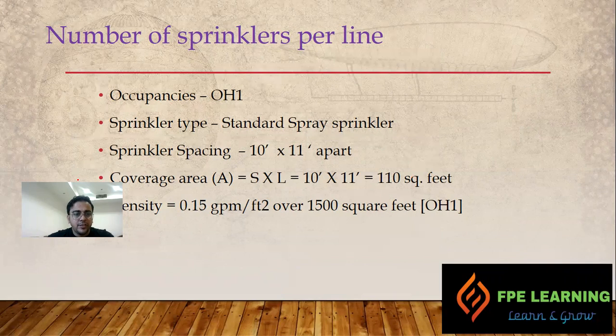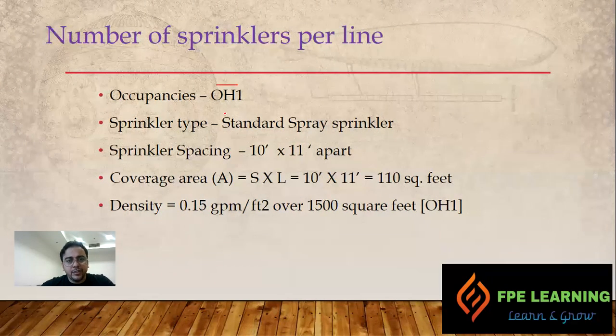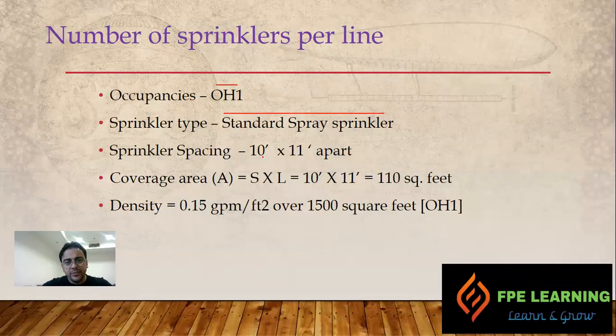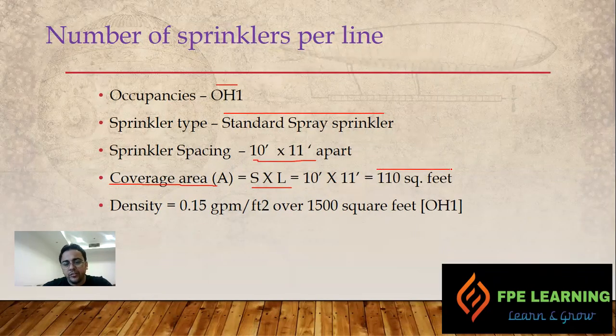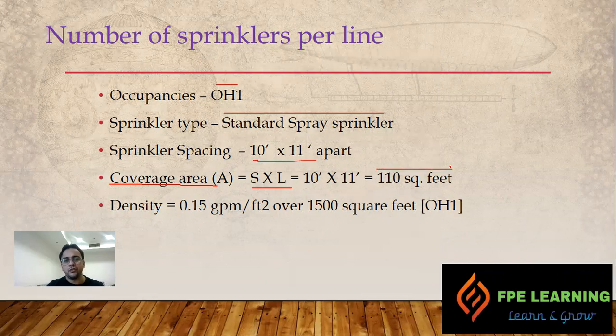Here is our case. Let's say our case is OH-1 for our project and we are using standard spray type sprinklers spaced at 10 feet by 11 feet. The area of sprinkler coverage equals S by L, so S is the distance between sprinklers and L is the distance between lines. One sprinkler can protect 110 square feet. Density for OH-1 is 0.15 GPM per square foot over 1500 square feet of area.